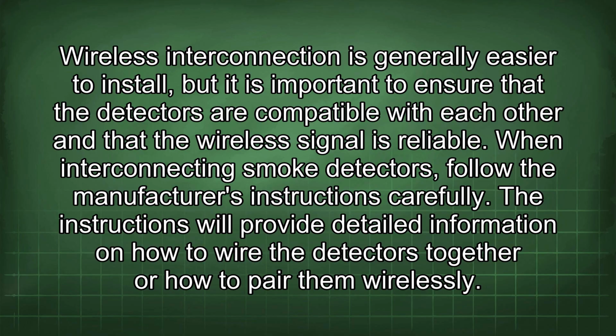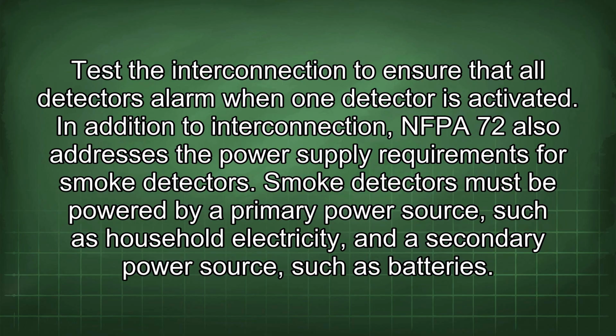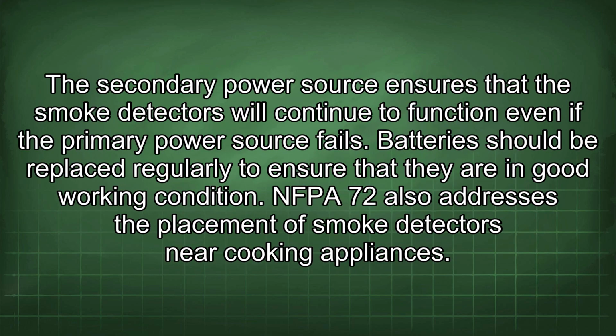When interconnecting smoke detectors, follow the manufacturer's instructions carefully. The instructions will provide detailed information on how to wire the detectors together or how to pair them wirelessly. Test the interconnection to ensure that all detectors alarm when one detector is activated. In addition to interconnection, NFPA 72 also addresses the power supply requirements for smoke detectors. Smoke detectors must be powered by a primary power source, such as household electricity, and a secondary power source, such as batteries. The secondary power source ensures that the smoke detectors will continue to function even if the primary power source fails. Batteries should be replaced regularly to ensure that they are in good working condition.